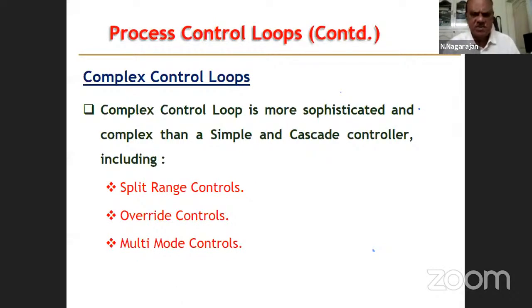Complex control loops are more sophisticated and complex than a simple and cascade controller. When you have so many variables in a process which are to be controlled in a simultaneous manner, then you have this kind of complex control loops. One is called split range control. You measure the variation and split the measured variable into two, say 0 to 50% and 50 to 100%. So 0 to 50% will be controlling one input and 50 to 100% will be controlling another input. So this is called split range, means you measure the parameter and the range is split into two. For one half of the range, it will operate one incoming parameter, other half will control another input parameter.